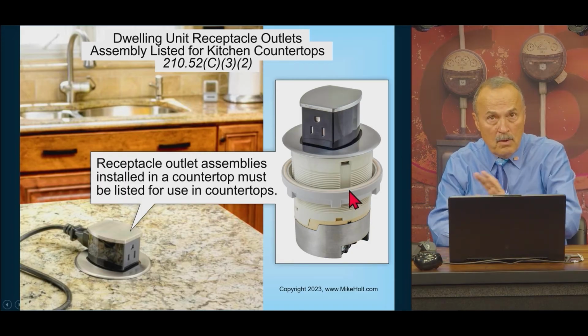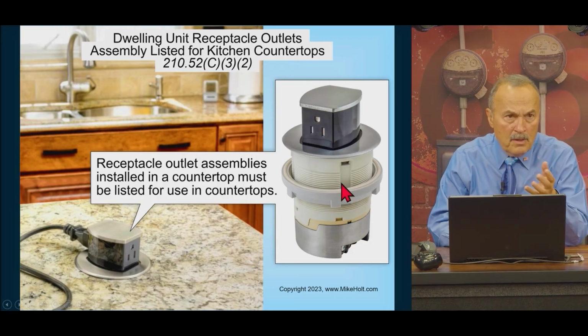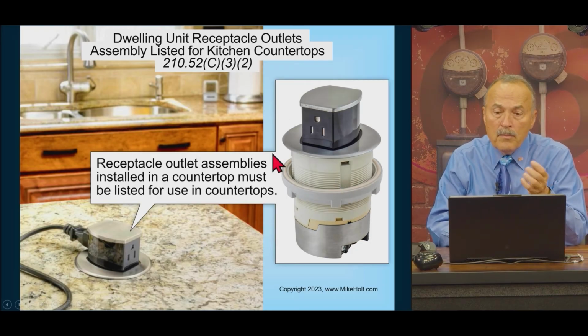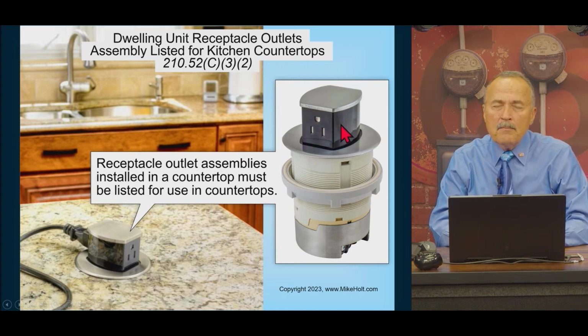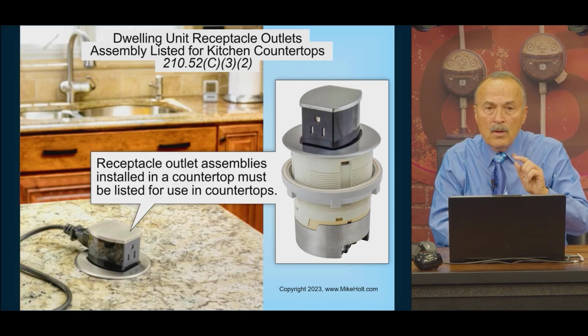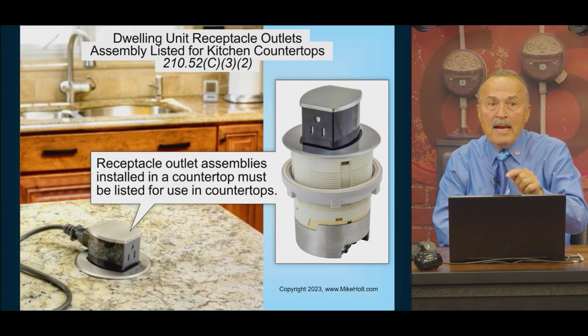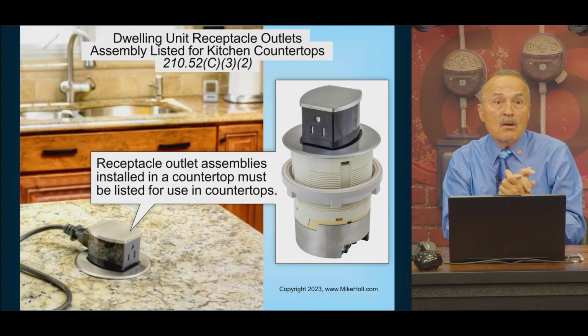Now, my understanding, Mario, you guys can correct me, is that this is made by Hubbell, and there might be others, but at least the ones we know of are Hubbell. You can see how this screws in and tightens inside here. This receptacle is listed to be installed in a countertop, defined, by the way, in Article 100, which I defy anybody to understand what it means. Or it can be installed in a workspace, which is a work surface. Yes, work surface. So these can be installed in both, because you might have places that are not kitchen countertops.